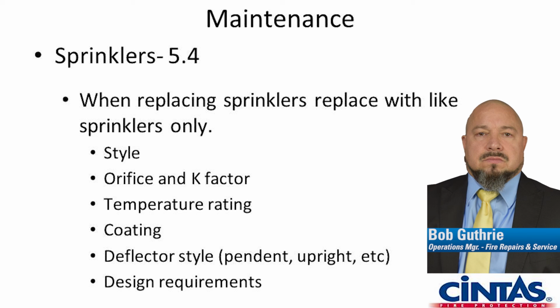Maintenance: when replacing a sprinkler, you replace that sprinkler with a sprinkler of the same style, orifice, and K factor. The style is going to be upright, pendant, sidewall, vertical sidewall. The orifice refers to the hole that's in the head, how much water is allowed to come through there. That's the orifice, and it has a corresponding K factor or coefficient. That coefficient is what we use when we're designing the system.